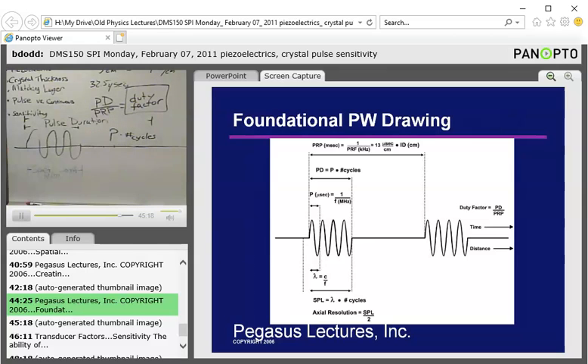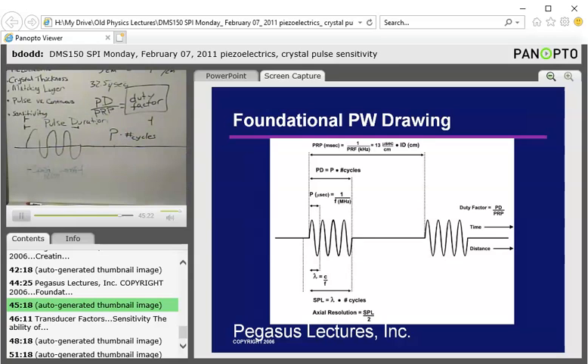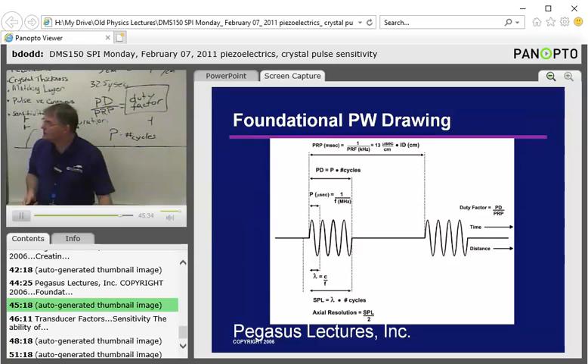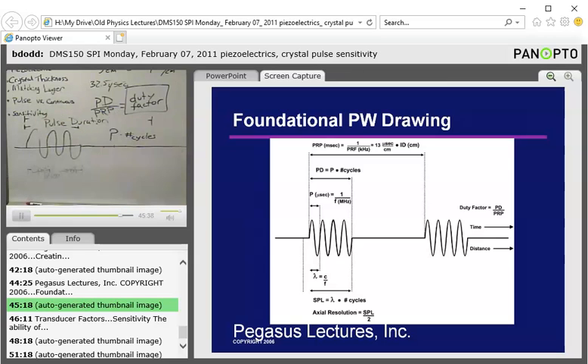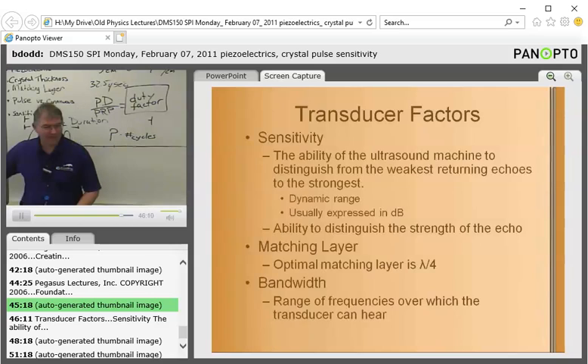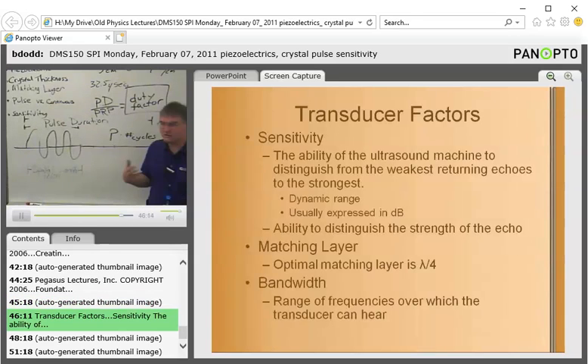And that pulse repetition period controls what? What does the pulse repetition period control? Depth, correct. Controls depth. I erased it. Okay. What does the pulse repetition frequency control? Depth, yeah. These are the same thing. Pulse repetition period and pulse repetition frequency are the same thing. They're just mathematical reciprocals of each other. So if you can control one, you can control the other. It's very simple. Now, I'm going to step off of this for right now, even though I know you guys are frantically writing down, but you don't have to, because we're going to come back to it again and again and again. And we're going to fill out that drawing until you know it perfectly well.